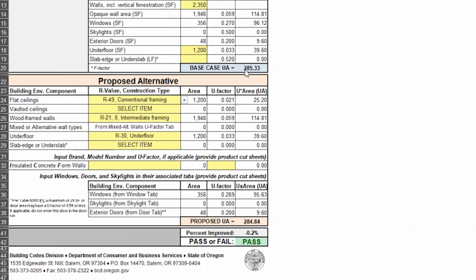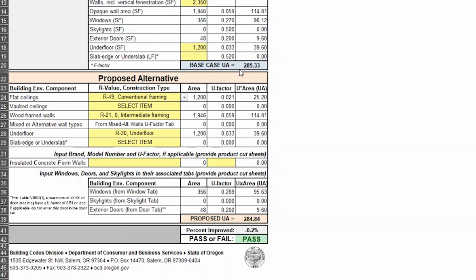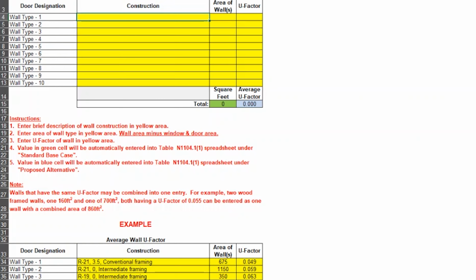And looking at this, the base case comes out to 285.33 for the U factor times area summed up. And then the proposed alternative comes out to 284.84, which is lower than the base case UA. So the total conductance over the total area of the building is better. The proposed UA is better than the base case. So this does pass. We don't have any special wall types.